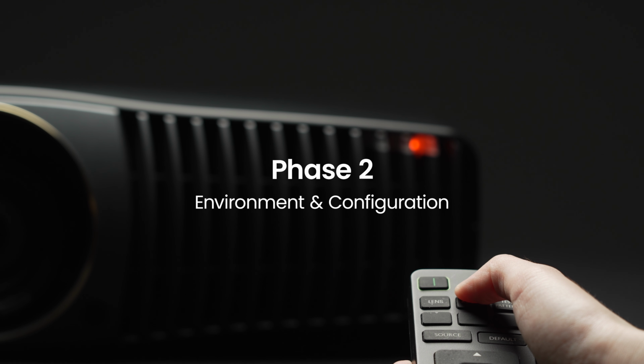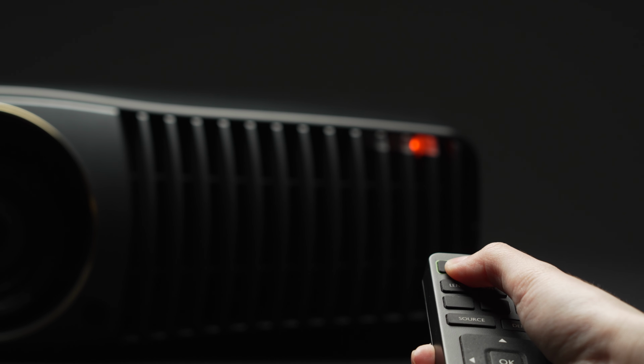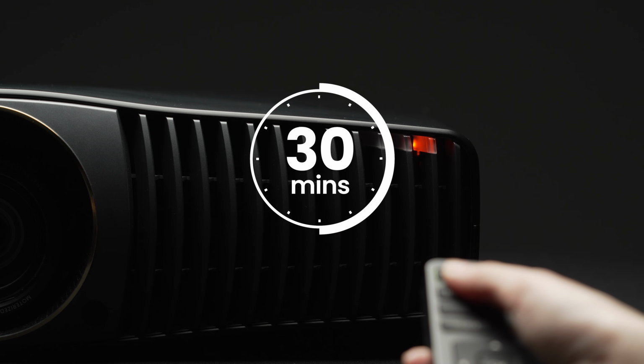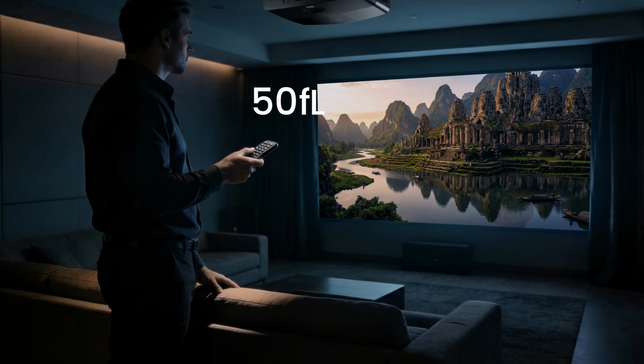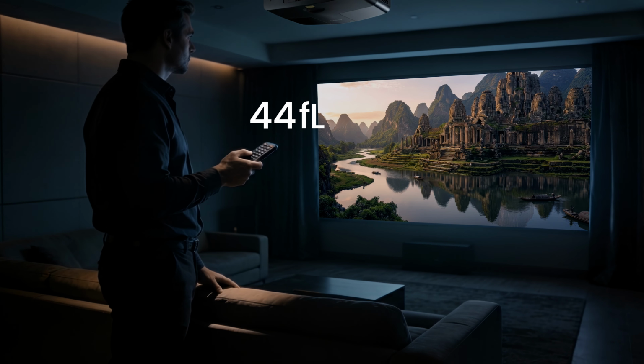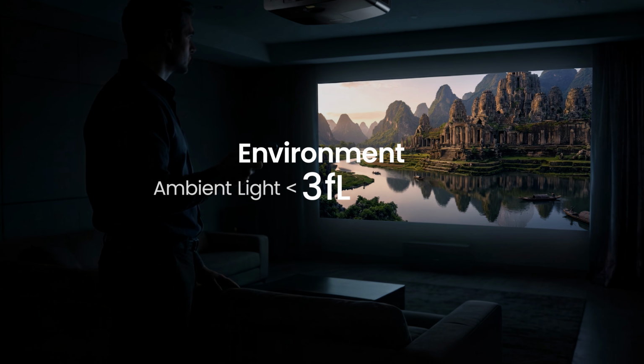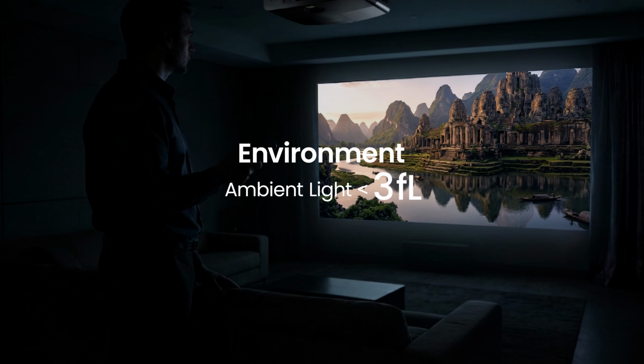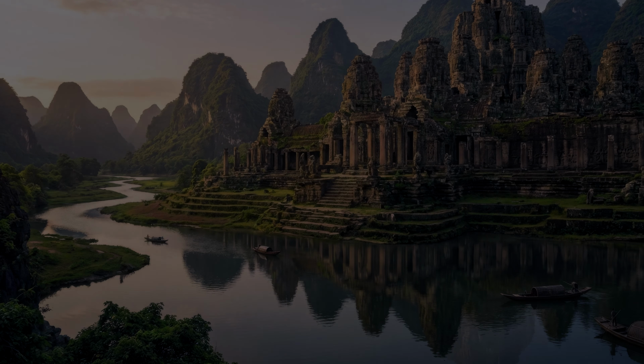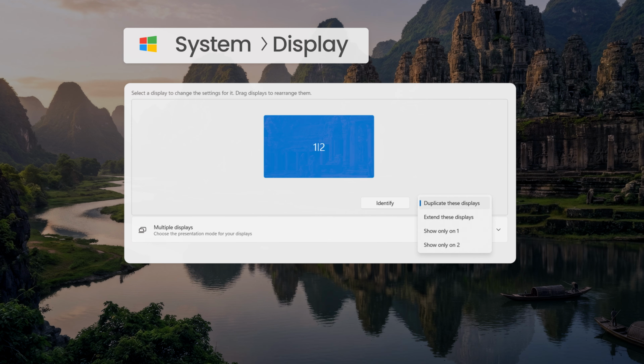Phase 2. Environment and Configuration. Power on the projector and allow 30 minutes for the system to warm up and stabilize. Darken the room to simulate actual viewing conditions and ensure the ambient light is below 3-foot Lamberts. Set Windows to extend these displays.